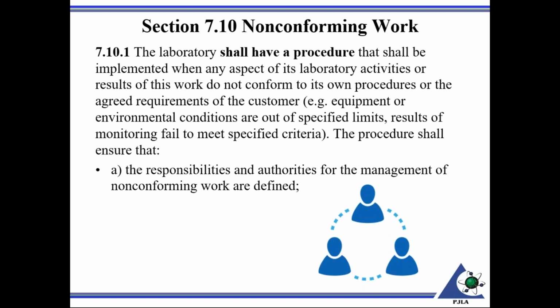So perhaps in your testing or calibration program protocol, you're required to list any predefined limits of acceptable environmental criteria. So let's say, for example, it was 20 degrees C plus or minus 4 degrees C, and it happened to be 6 degrees C out, and you proceeded with the calibration. It was not discovered until after the fact. That would be an example of non-conforming work.